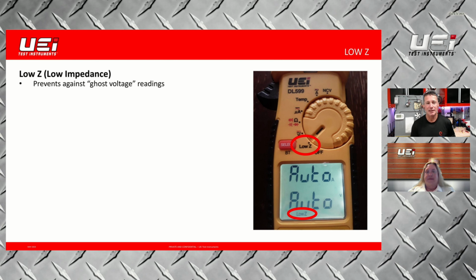Awesome, yeah, that's the thing we started seeing, especially when we started having VFD drives and inverter controls, when we had voltages being diverted through controls. So we can pick up some additional ghost voltages. Especially when we have a lot of conductors intermingled in small chases. Exactly, and there's a lot more wires in a lot smaller places nowadays. Yeah, absolutely, very good addition.